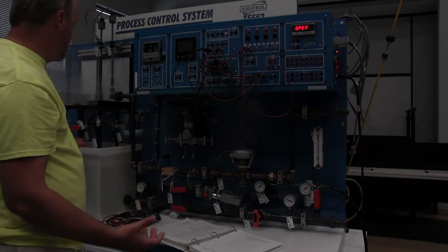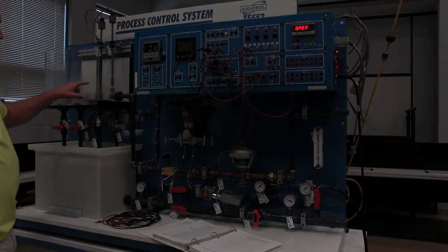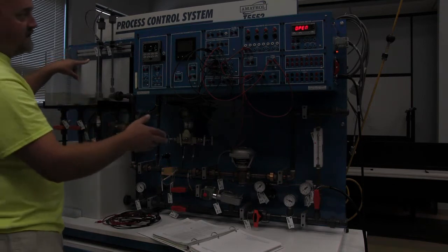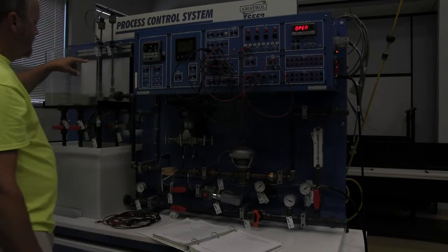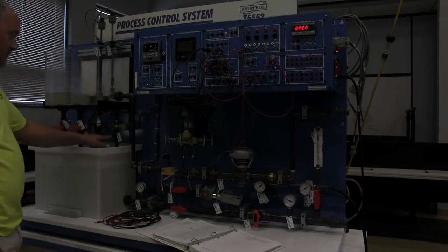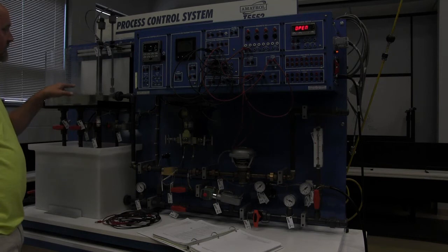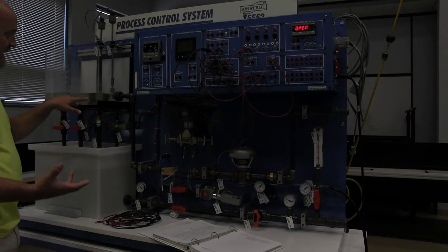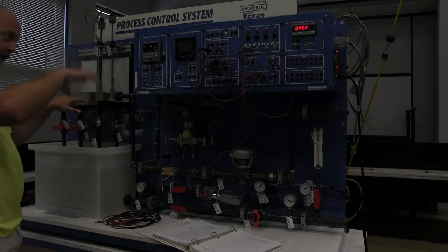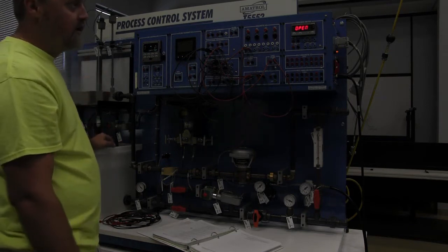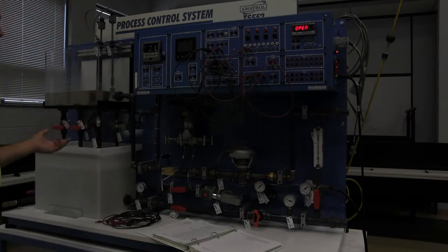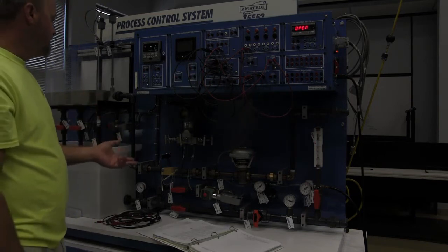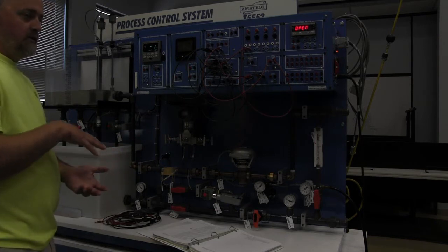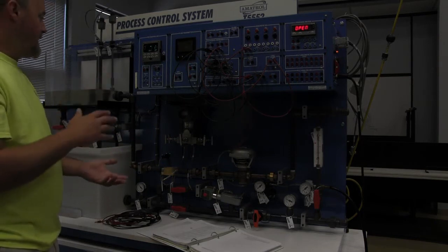As this process tank is filling, when the higher float of the two gets made, this process pump should shut off. It should open a solenoid valve and drop back down till both of the floats are down. Then the pump will turn back on till both of them are up. It's going to turn off and keep repeating itself as needed. So this would be how you would fill a ground storage tank, or you would fill a wet well in a lift station.